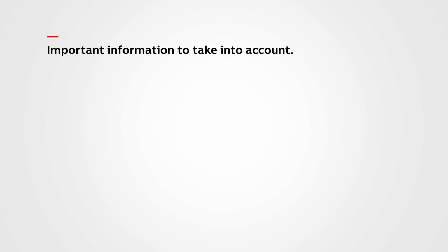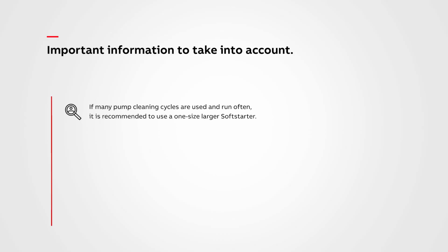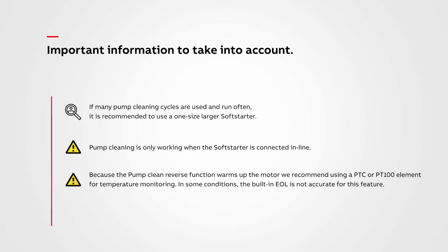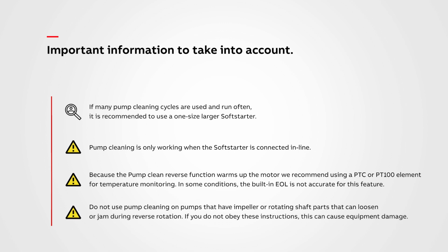Important information to take into account. If many pump cleaning cycles are used and run often, it is recommended to use a one-size larger soft starter. Pump cleaning is only working when the soft starter is connected in line. Because the pump clean reverse function warms up the motor, we recommend using a PTC or PT100 element for temperature monitoring. In some conditions, the built-in EOL is not accurate for this feature. Do not use pump cleaning on pumps that have impeller or rotating shaft parts that can loosen or jam during reverse rotation. If you do not obey these instructions, this can cause equipment damage.